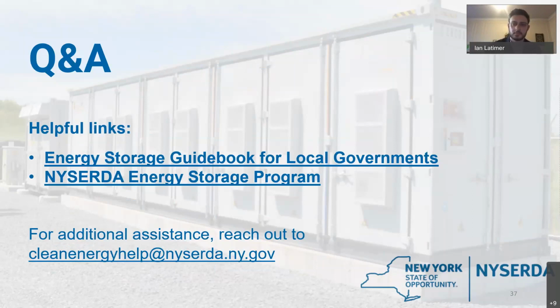That's a really good question, and I was remiss not saying that. When these lithium-ion battery cells do go on fire, they come out as a pretty intense fire with a lot of pressure. It's almost like a pressure fire, and it's going to be very hard to put out, even if you were able to get access to the batteries themselves to get water directly on them, which is our challenge. If you're outdoors and these cells are in watertight modules inside a watertight enclosure, how are you going to get water on the inside of these things? So that becomes a challenge. But these things are very intense, and that intensity is also based on the state of charge of the batteries themselves. High state of charge means more energy that needs to be released.